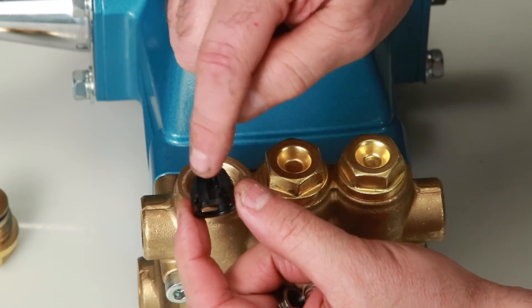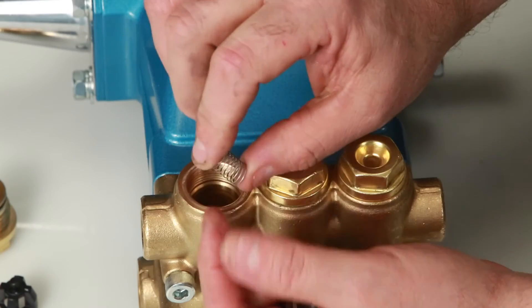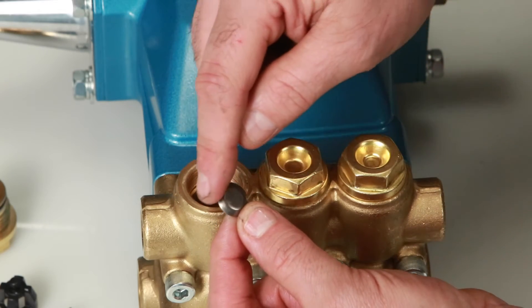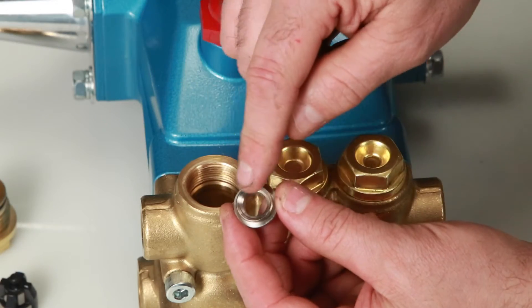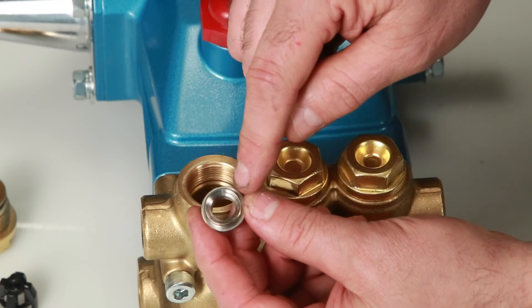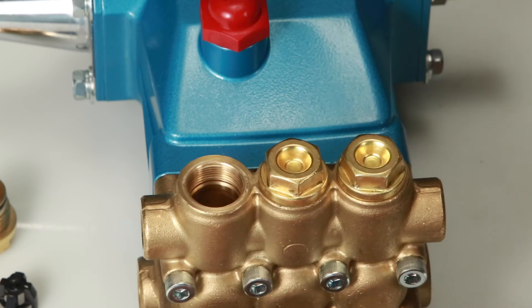Next, inspect spring retainer for cracks, excessive wear, or damage. Inspect spring for proper tension or any damage. Inspect tapered surface of the valve for wear, pitting, or damage. Inspect tapered surface of valve seat for wear, pitting, or damage. Pitting on the valve seat or valve is an indication of cavitation.